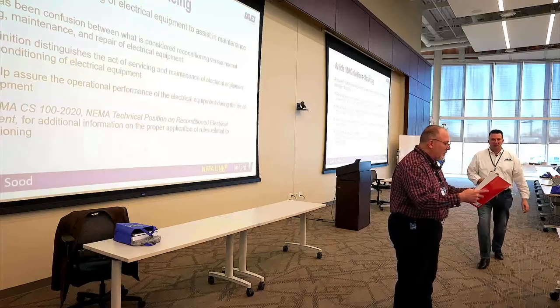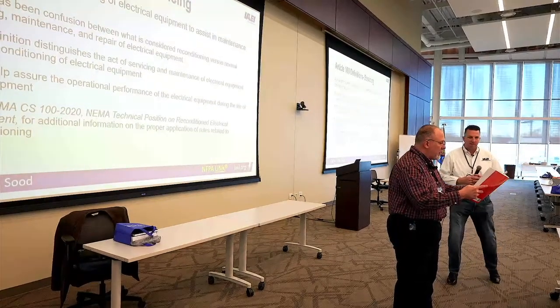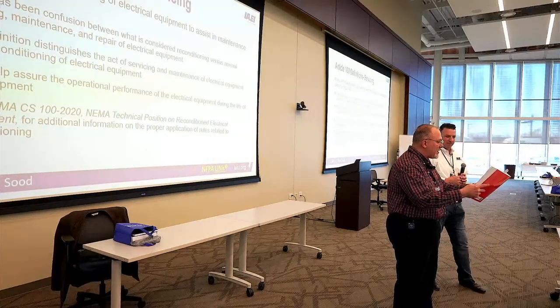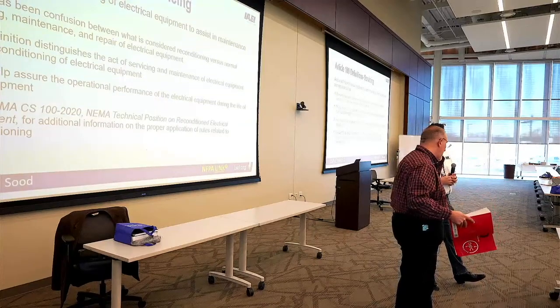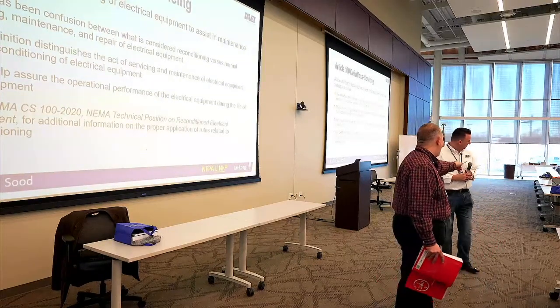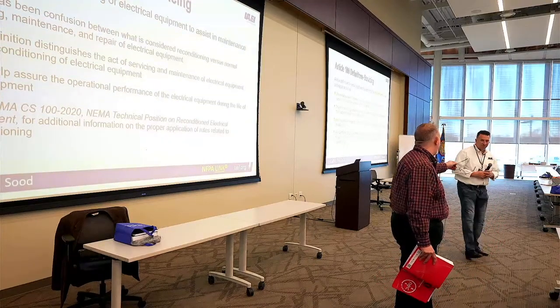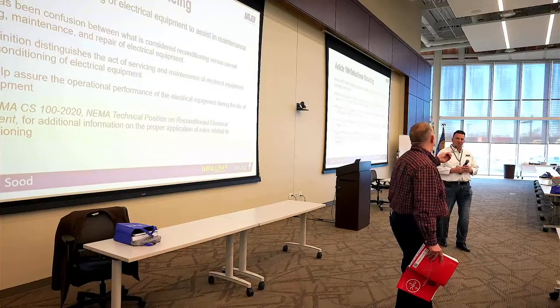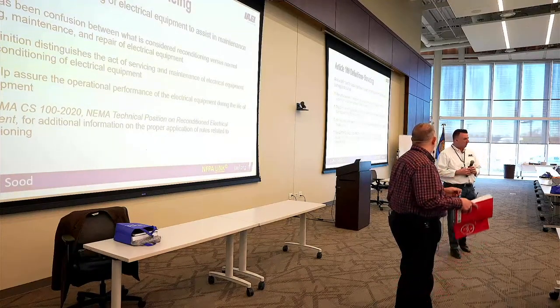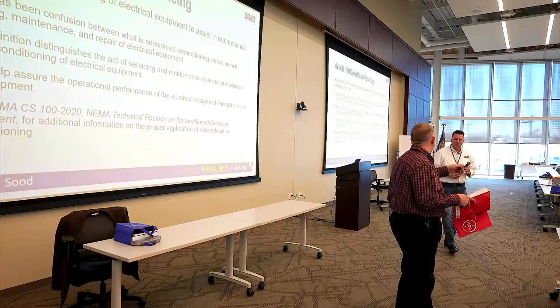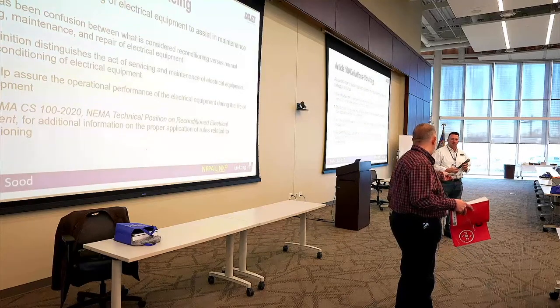But in any case, if it's required to be listed, equipment reconditioned required by this code to be listed shall be listed or field labeled. So you can get, I think UL, ETL, a few others have field evaluation bodies that would do the field evaluation for equipment that's reconditioned in the field, right? Oh yeah, I'm getting the nod.